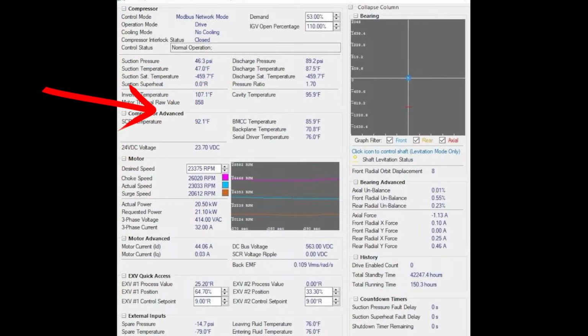Now, I don't want to oversimplify this. I'm sure that Danfoss is probably going a little bit deeper than what I'm actually explaining here, but my goal is to give the basic core concept of how they're dictating what these speeds should be and what these speeds mean in relation to surging. So one of the reasons why this surge is lower RPM is because if our pressure ratio remains the same and constant at 1.7, but we lower our speed too much, then we have pushed over into our surge line.